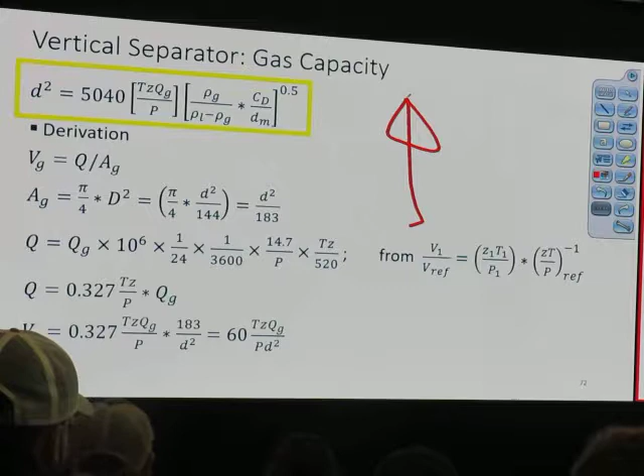Maybe the way that this comes from is based on terminal velocity and actual velocity inside. Actual gas velocity is volumetric flow rate divided by the cross-section area of the flow. That is the actual velocity going up. Settling velocity is another equation, the terminal velocity equation. We compare those two and make them equal to each other, Vt equal to Vg, then rearrange, and we get that. So the gas capacity equation is based on settling velocity and the velocity of gas inside. If settling velocity is more, it's good. If the gas velocity going up is more than the settling velocity, it's not good. We're going to plug or saturate the mist extractor. Make sense to you? So we compare those two.